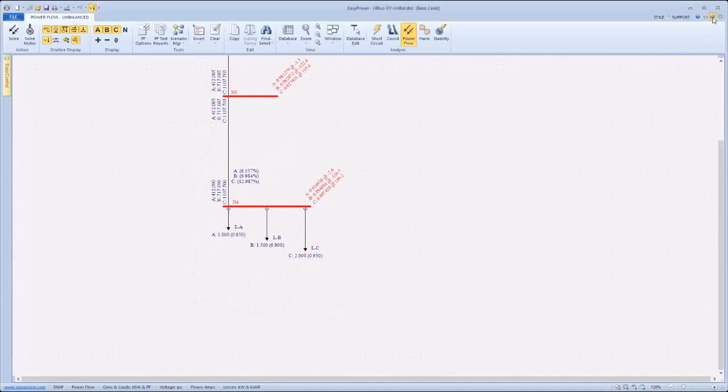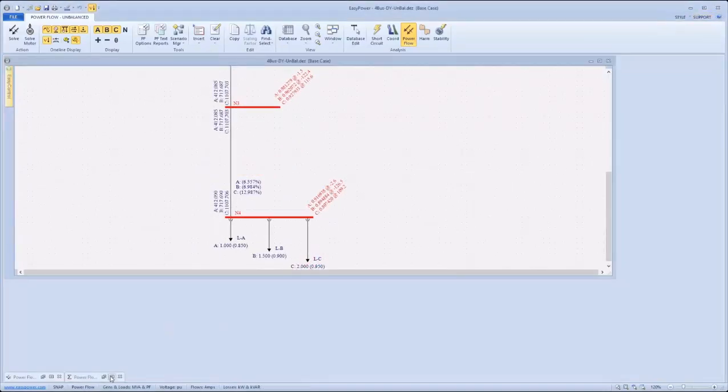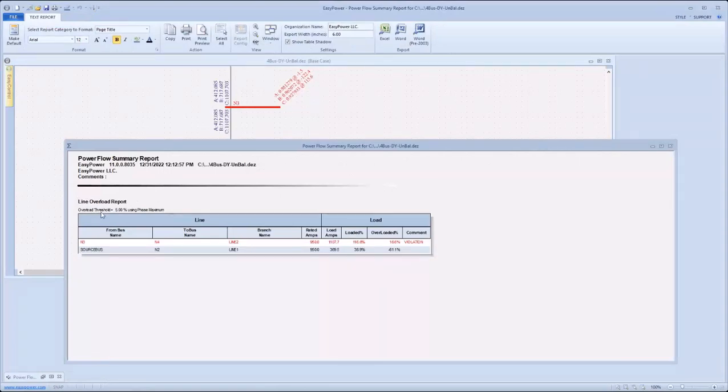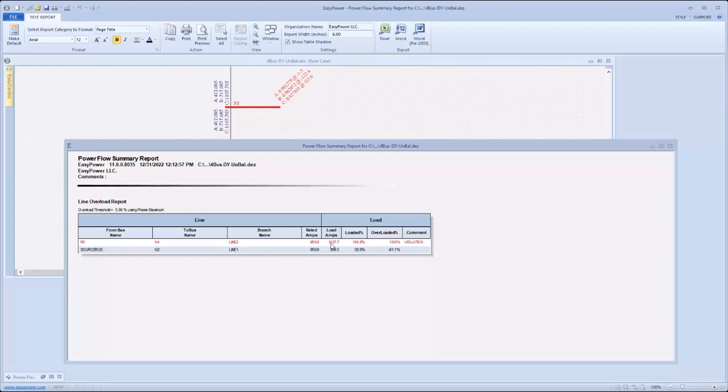Taking a look now at the summary reports that were generated. In this case, only the line overload report was generated, and it's using an overload threshold of 3% based on the maximum phase current. As can be seen, the branch from bus N3 to N4, line 2, is overloaded at 1,107 amps.